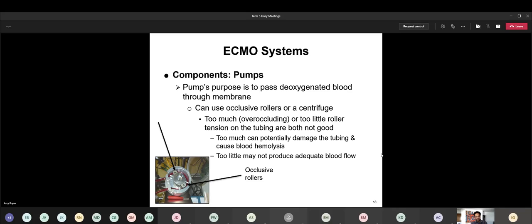But then, of course, sometimes they're having to give blood products as well. They're having to hang blood. And again, all of this has got to be monitored very carefully, and they have to make adjustments as they need to. And then there's a necessary balance between over occluding and under occluding. So if they don't have these adjusted and the rollers are just barely squeezing the tubing, then we know that's going to limit the amount of blood flow through the circuit. So then if it's not the occlusive roller type of pump, then it's going to be a pump that just spins and spins and spins, using centrifugal force to make the blood move.